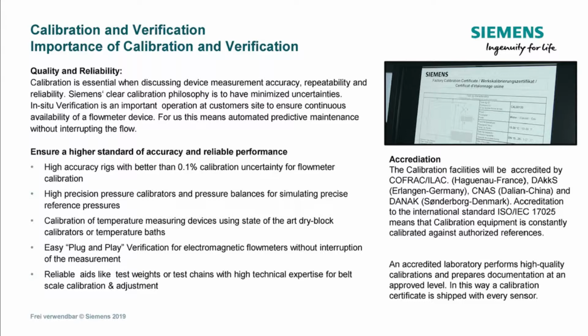High accuracy rigs, with better than 0.1% calibration uncertainty, for flow meter calibration. High precision pressure calibrators and pressure balances for simulating precise reference pressures. Calibration of temperature measuring devices using state-of-the-art dry block calibrators or temperature baths. Easy plug-and-play verification for electromagnetic flow meters, without interruption of the measurement. Reliable aids like test weights or test chains, with high technical expertise for belt scale calibration and adjustment. An accredited laboratory performs high quality calibrations and prepares documentation at an approved level. In this way, a calibration certificate is shipped with every sensor.